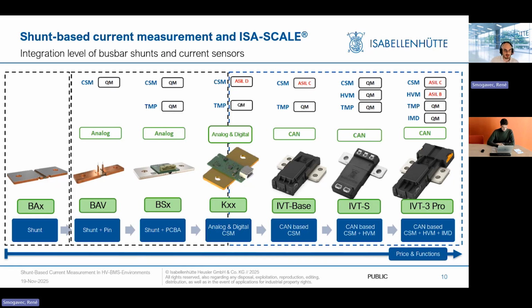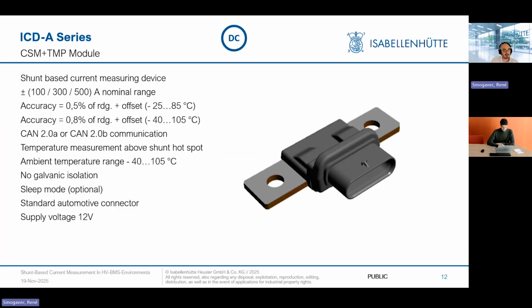So you don't need to invest in more components than just our one that we offer. The ICD-A is one of the two ISA-SCALE products that I want to show you before we go into a big application example for choosing the right component. We have the ICD-A as our most compact active sensor, which features a known connector, the Tyco MCON. It features one channel current measurement at plus minus 0.5 to 0.8% reading tolerance plus offset. So depending on the measurement range, in that case the measurement range goes up to plus minus 500 amps. So it is also not suitable for very high currents that might occur in the environment.